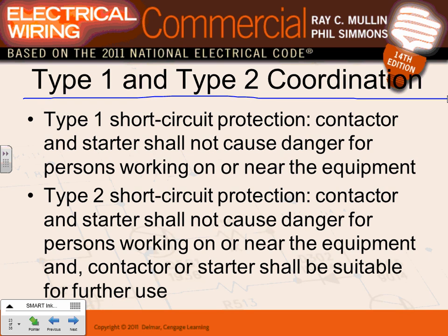So type 1, the equipment will not explode, it's safe, but you might have to go replace everything. Type 2, it's safe, doesn't explode, and it keeps the equipment for the most part intact. So that's mostly for control equipment.